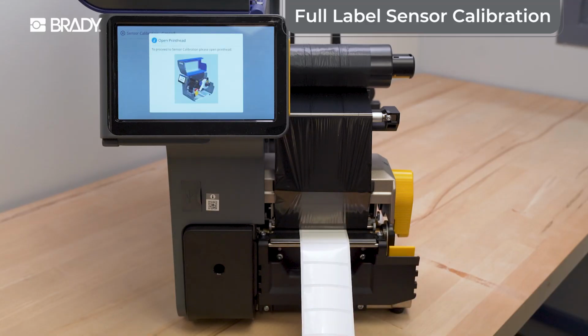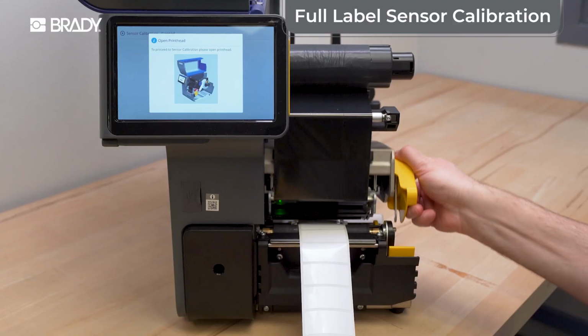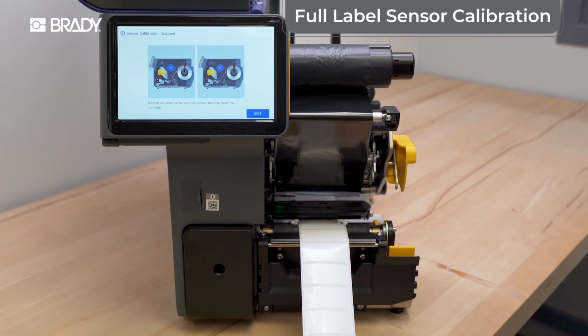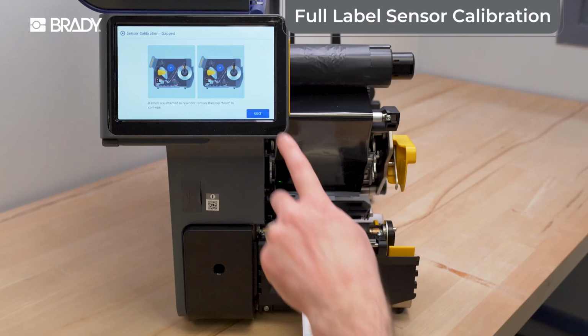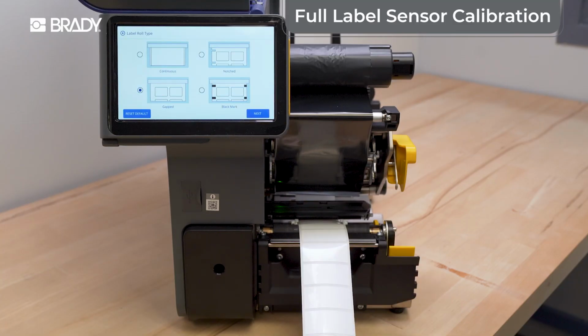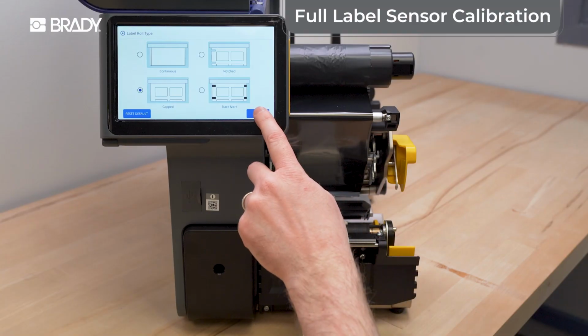The following prompts are very similar regardless of the print mode that you are in. Only minor differences occur. Follow the prompts on the screen. For this example, we will show the prompts used in peel mode. Open the printhead, following the prompts on the screen. If any material is attached to the internal rewind spindle, be sure to remove it at this time. If not, tap the Next button. Verify the type of roll that you have installed, continuous, notched, black mark, or gapped. We're using gapped. Tap Next.